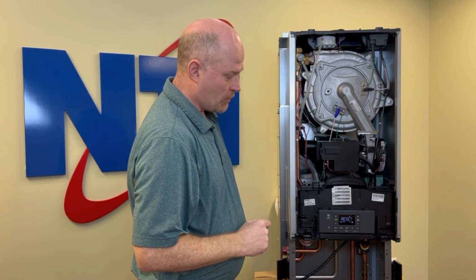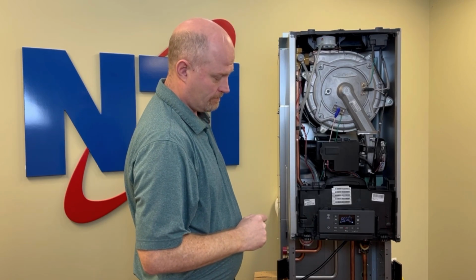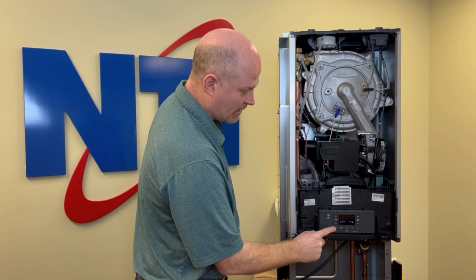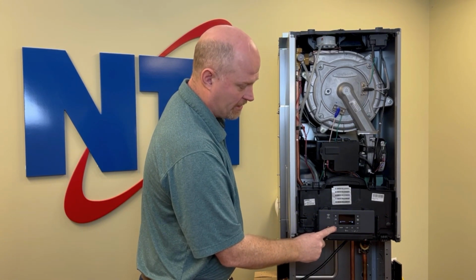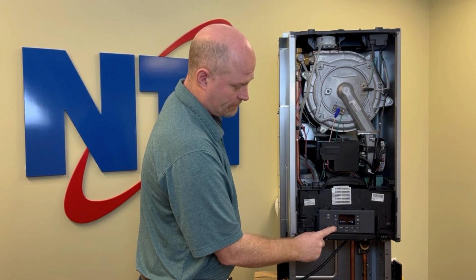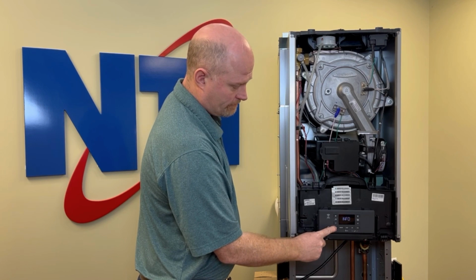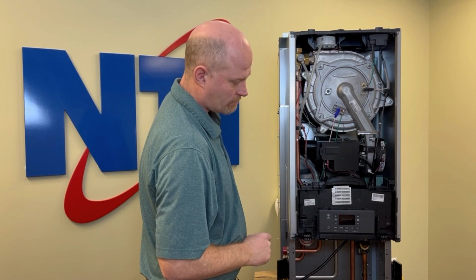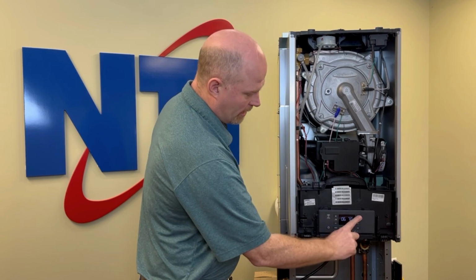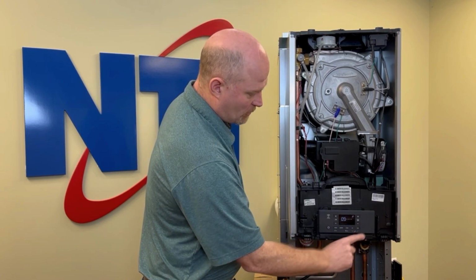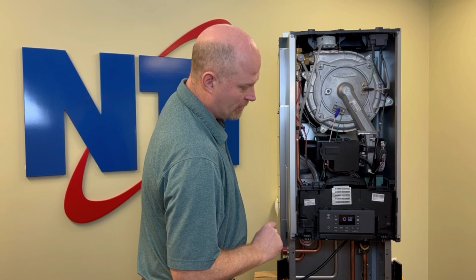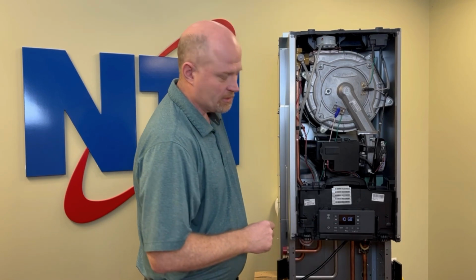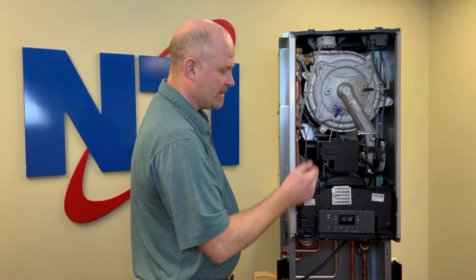Let's reset the error code. It did reset this time. I'm going to go in and double check my temperature reading on the boiler. And this time when we navigate up to menu number 10, we can see the flue gas temperature is 68, which in this case is accurate.